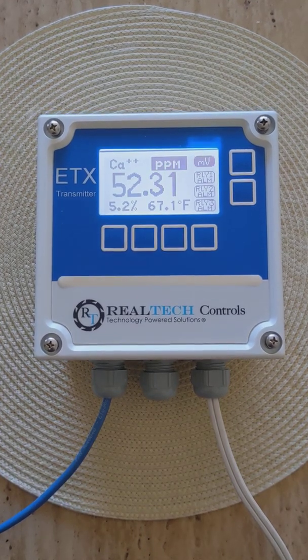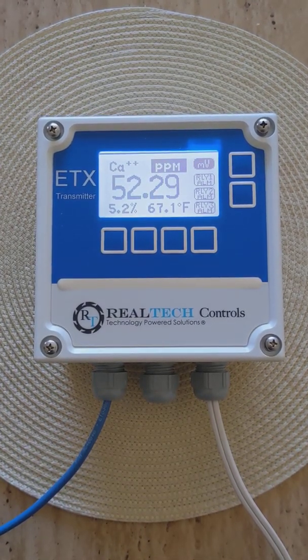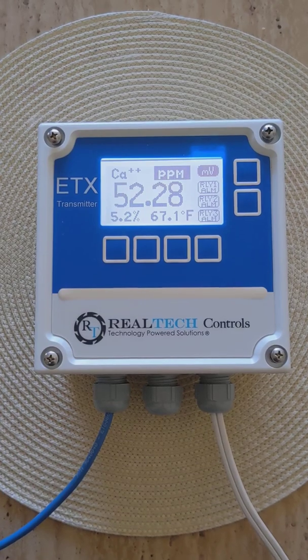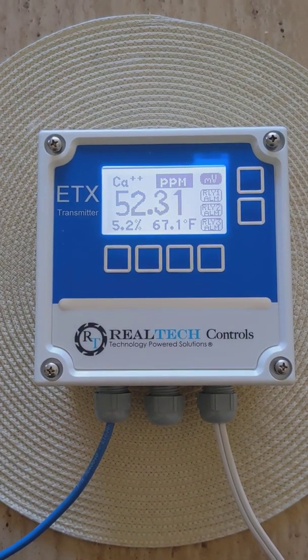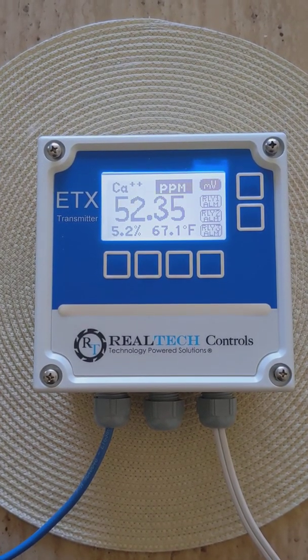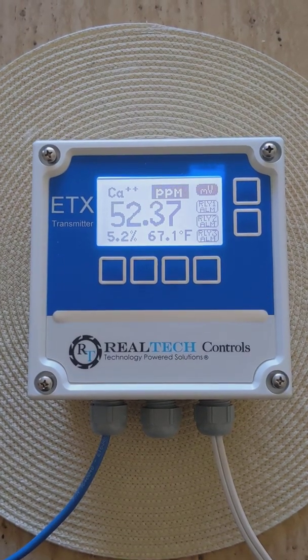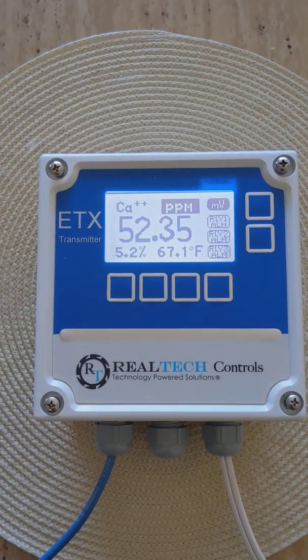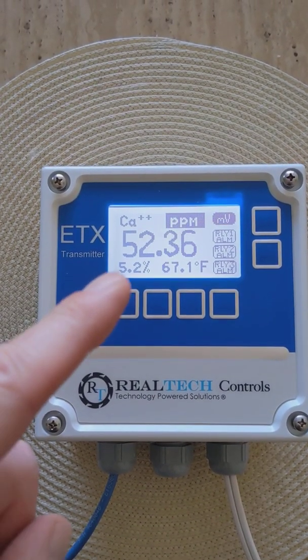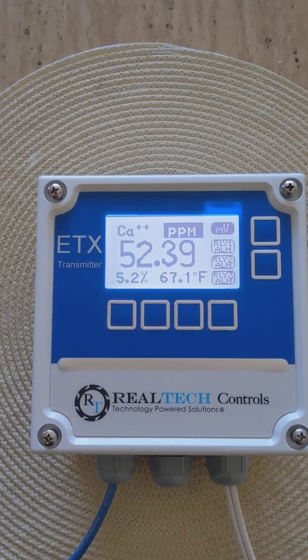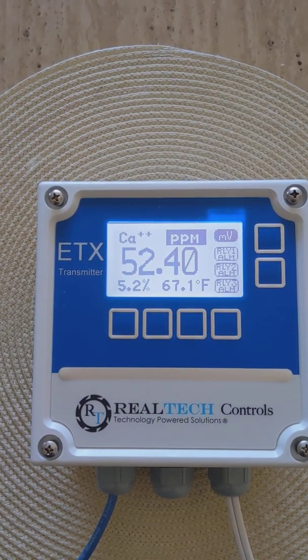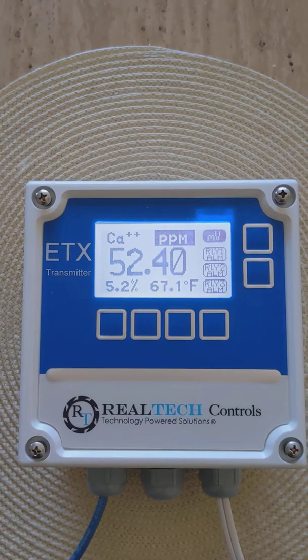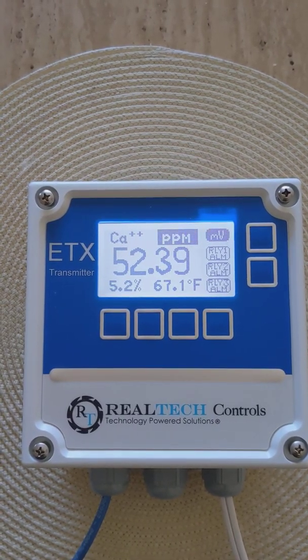My name is Julian with RealTech Controls, and I'm going to show you how you do a 2-point calibration with the model ETX Water Hardness Analyzer. At the moment I'm reading 52 ppm, 5.2 as a percentage of my 4 to 20 milliamps, so probably around 5 milliamps, and 67 degrees F.